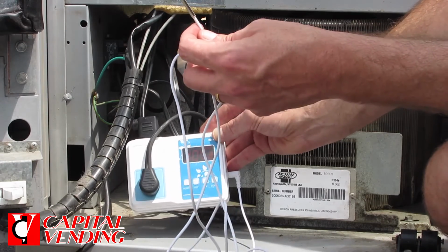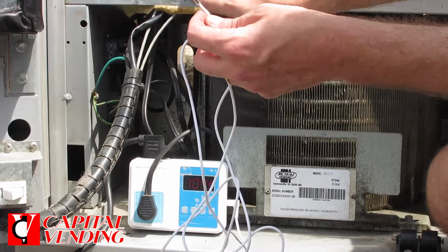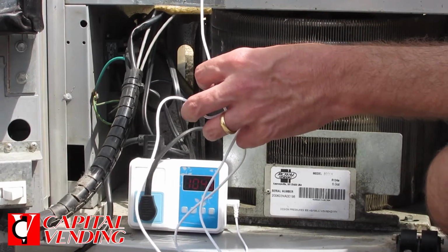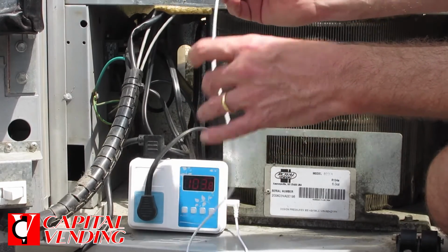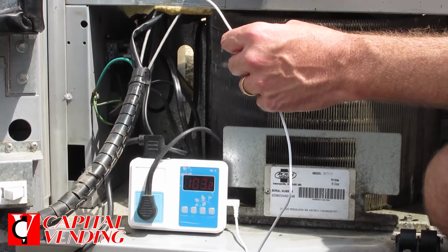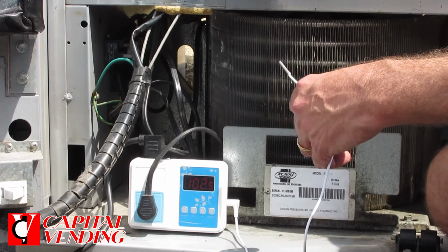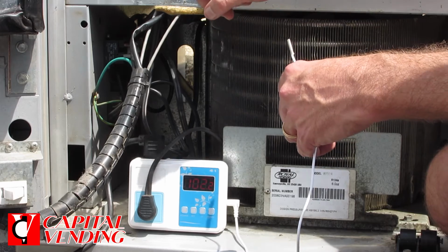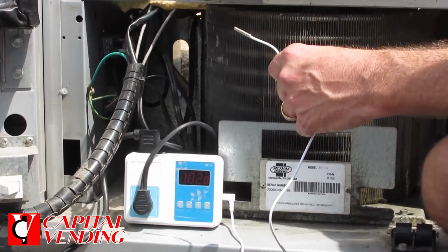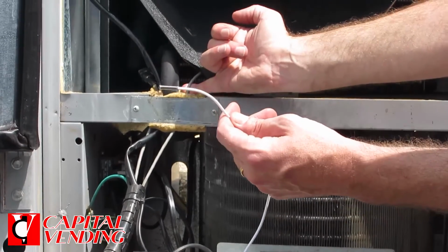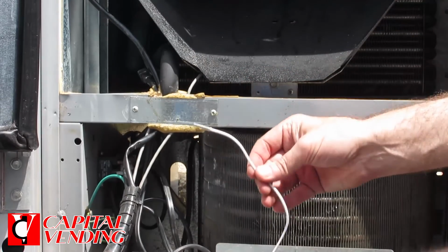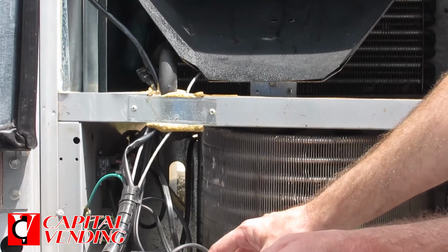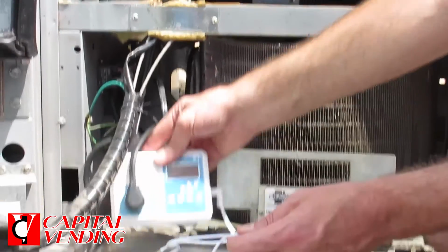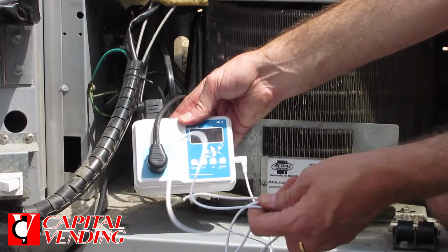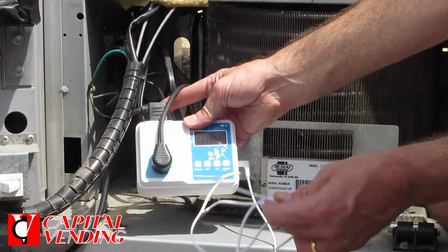To do this installation correctly, you're going to want to take this plate off. This must absolutely be in the cold section of the machine. What you could do is follow this gray wire, which is typically on the existing temperature probe, back to where the machine's temperature probe is placed, and place this one there. Then bundle this wire nicely and keep it with the system. Once you put in the replacement parts and everything's working, this unit can be taken out and used to help you troubleshoot and fix your next machine.